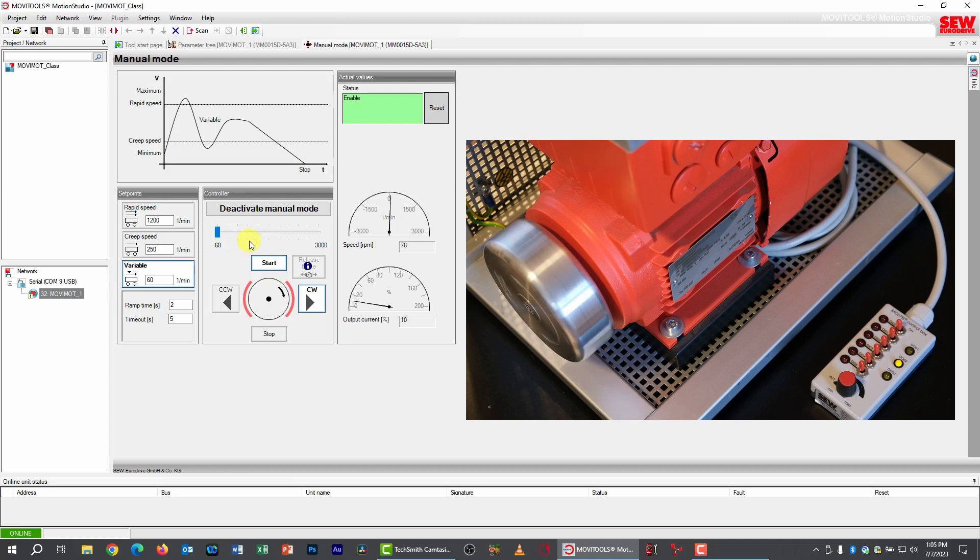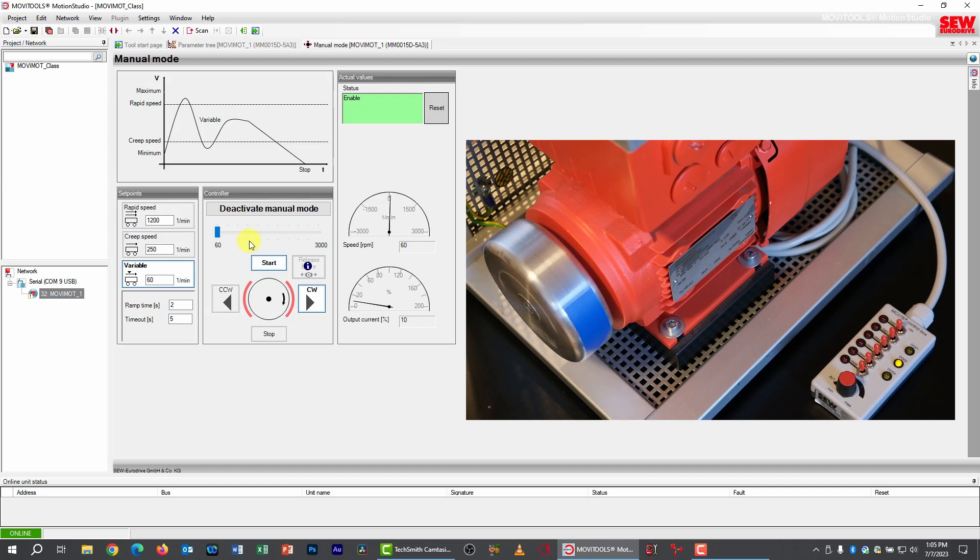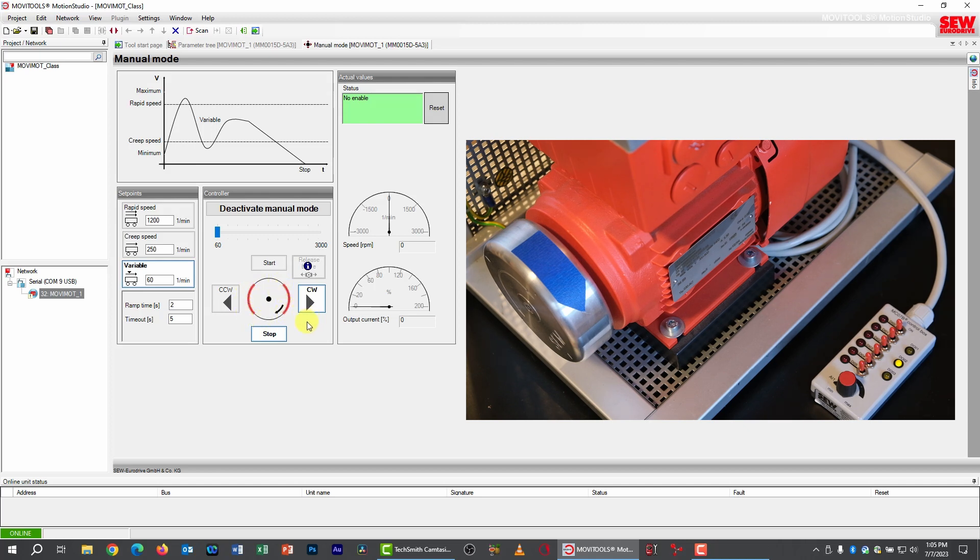We can go back to the slider control by clicking variable, and just slide this all the way down. Notice that the motor doesn't actually come to a complete stop. That's because the minimum speed is setting a lower limit. I'll show you how to change that in just a minute. Let's stop our drive here. You notice our brake symbols now show that the brake is engaged and is holding the motor fixed. So that is basic manual mode operation. This gives us a very good way to exercise our drive.